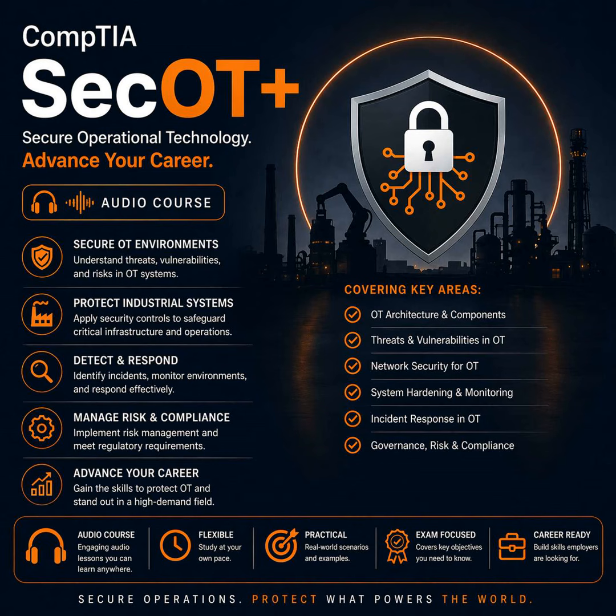Understanding what you own versus what you inherit requires clear thinking about control levers, meaning what you can directly change and what you can only influence. You may not be able to change the firmware of a legacy controller immediately, but you can often change the network pathways that reach it, the accounts that can access it, and the monitoring that watches for unusual behavior. You may not be able to redesign the entire plant network at once, but you can often strengthen one boundary, reduce one unnecessary conduit, or create a controlled remote access landing zone. You may not be able to rewrite vendor code, but you can require vendor session logging, time-limited access, and vulnerability notification processes.